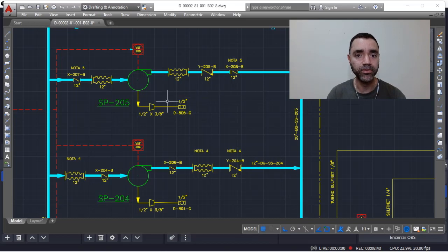Another thing to observe here is that we are talking about rotating equipment, and because of the nature of this equipment, we can have vibration. Small vibration is allowed. It's not an issue for the equipment, but this vibration connected with the pipes can lead to a higher vibration and some kind of resonance in the system.